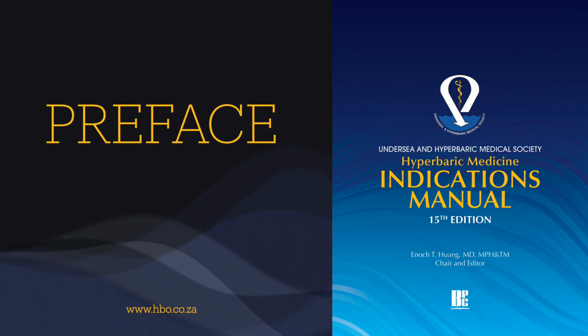Now Class A, multiplace. A Class A system is different. It's a multi-place chamber, designed to hold 2 or more people at the same time. Patients, observers, maybe support staff like nurses or techs. In this system, the manual explains, the chamber is pressurized with compressed air. With air? Yes, compressed air, while the patients inside breathe near 100% oxygen through individual delivery systems, things like masks or special head hoods, or via endotracheal tubes if they happen to be intubated. So that allows staff to be safely inside the chamber with the patients, breathing air to avoid oxygen toxicity themselves while the patients get their therapeutic oxygen dose.